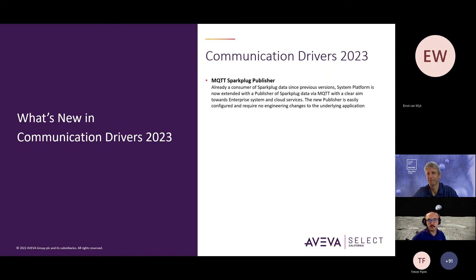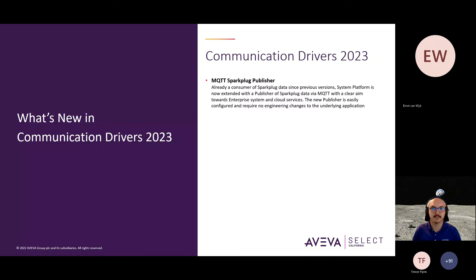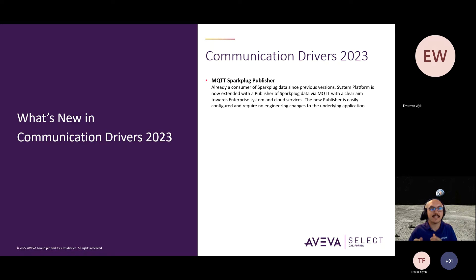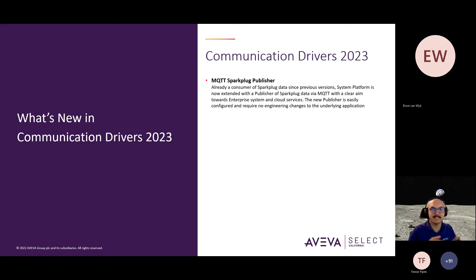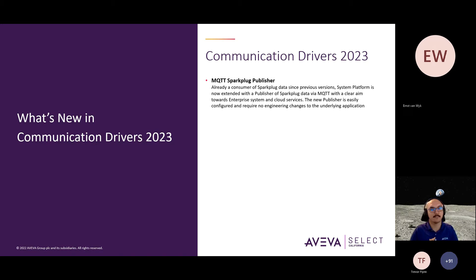Just touching really quick base on the communication driver updates with the new version release of 2023. With the 2020 R2 release, we added MQTT with a Sparkplug B specification as a subscription to a broker. But now the same driver has the ability to make a published connection to that same broker using that Sparkplug B specification.